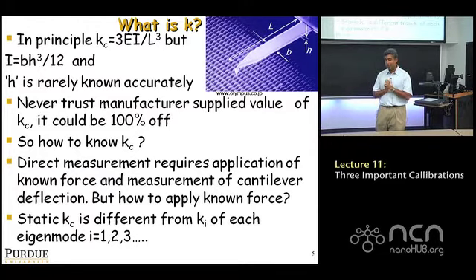So the question is, how do you apply a known force? The objective should be to apply, let's say, 10 nanonewtons of force and measure the deflection. So you're stuck, because we don't really have standards. There is, in fact, no method to generate a standard force of 10 nanonewtons. It doesn't exist. And this is the problem. So many indirect methods have been developed to calibrate cantilever stiffness.